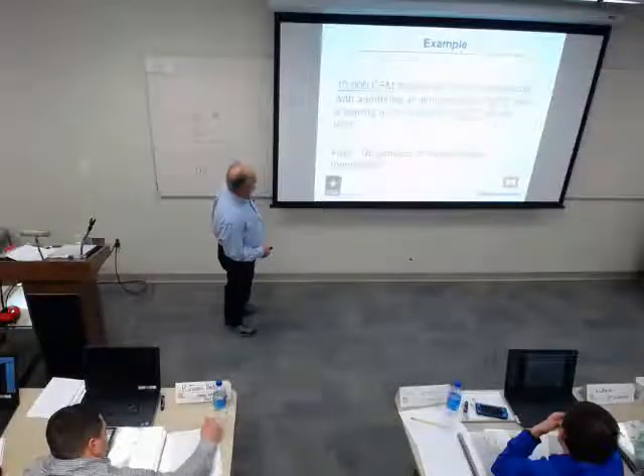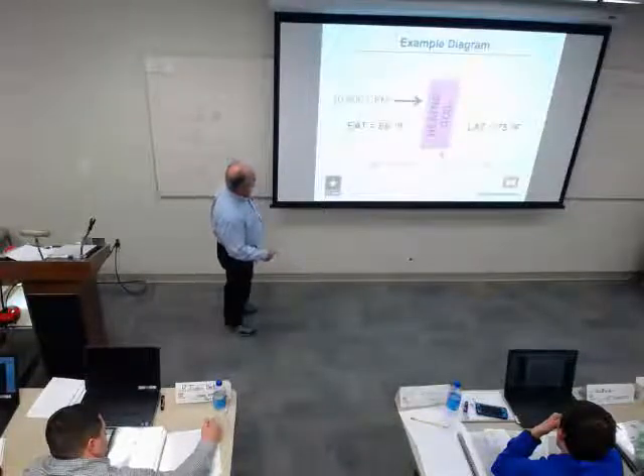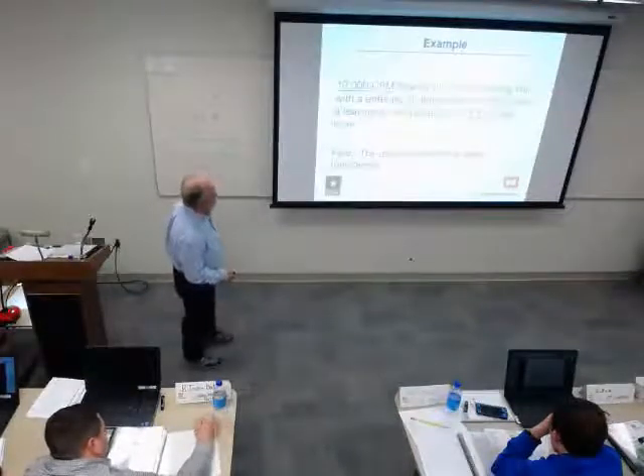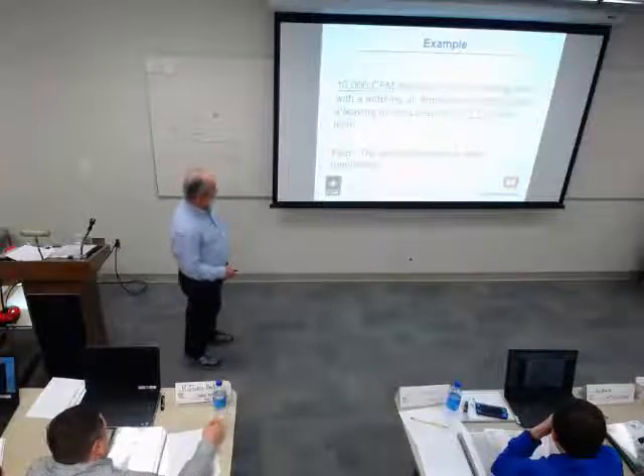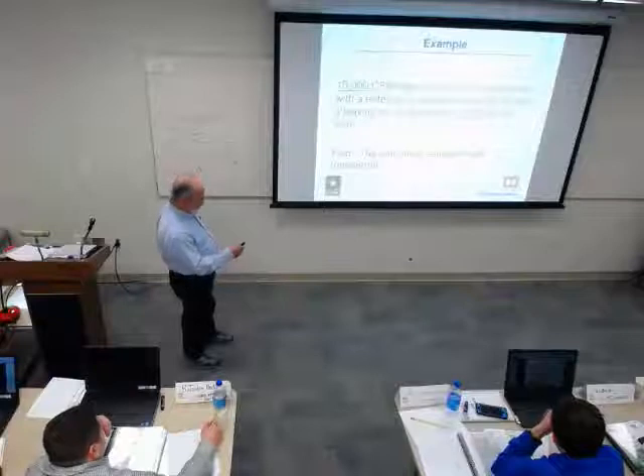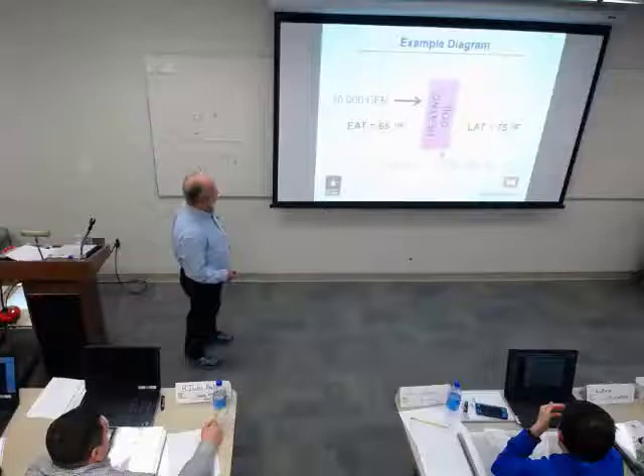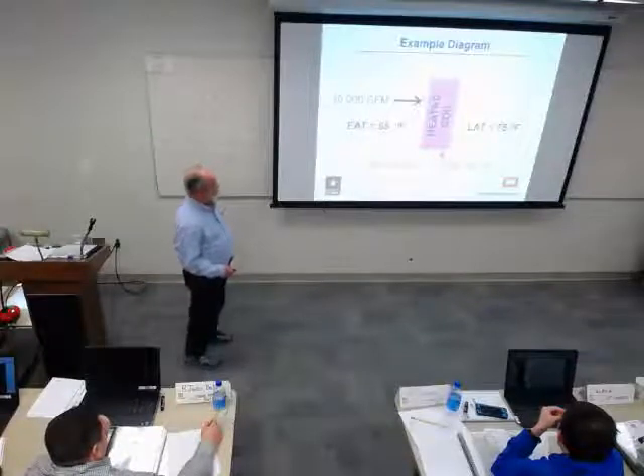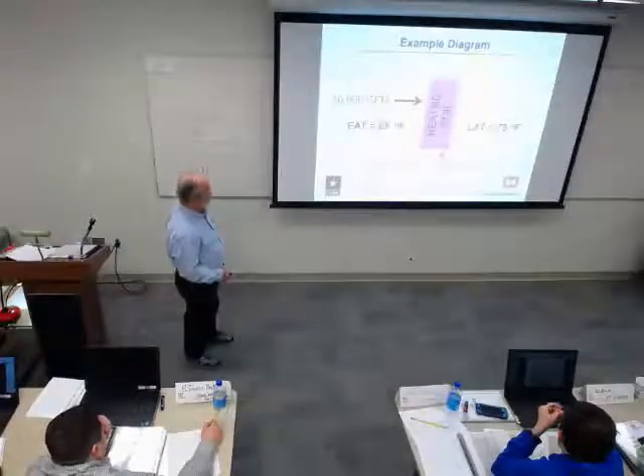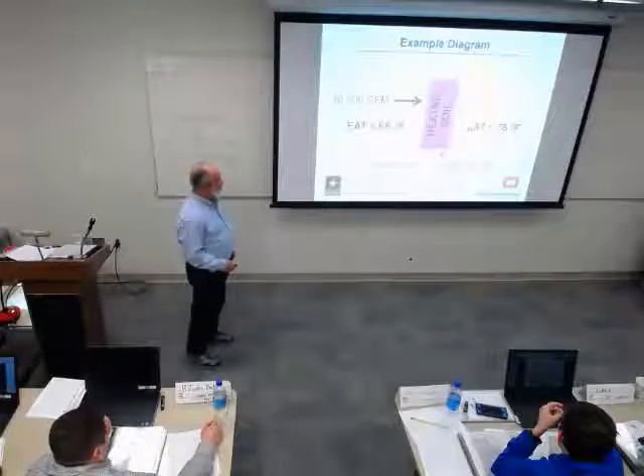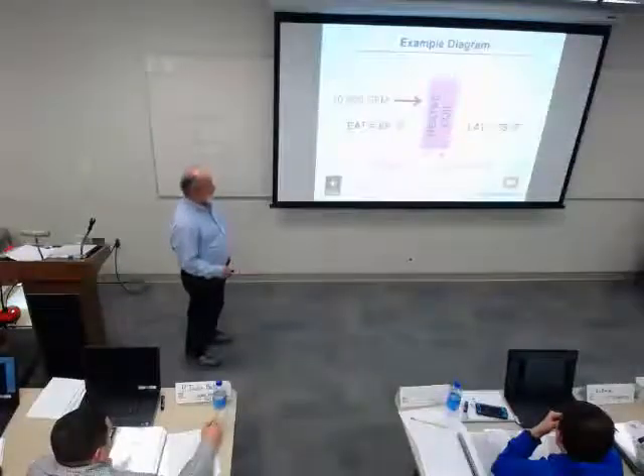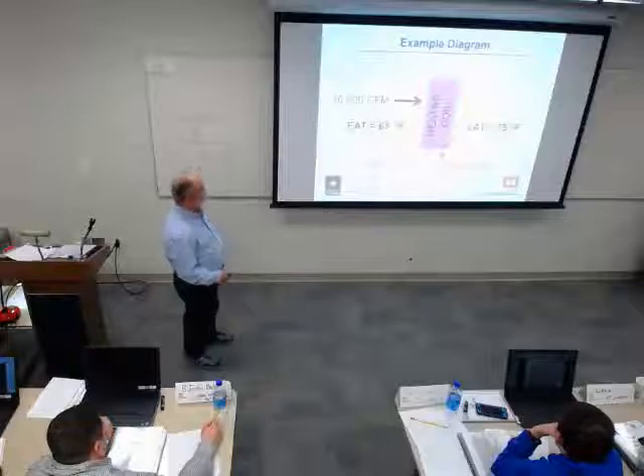So let's see here. Okay, so we have 10,000 CFM flowing through a heating coil with an entering air temperature of 65, leaving air of 75 at sea level. And we want to know how much heat is transferred. So here we go. We have 10,000 CFM of air coming in. It is 65 degrees. We're heating it, and it's leaving at 75 degrees.